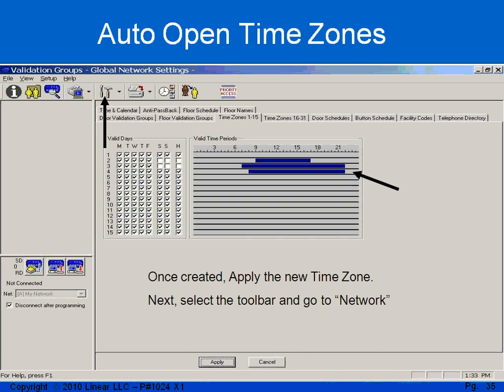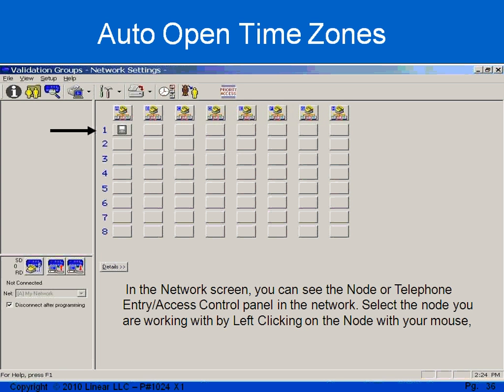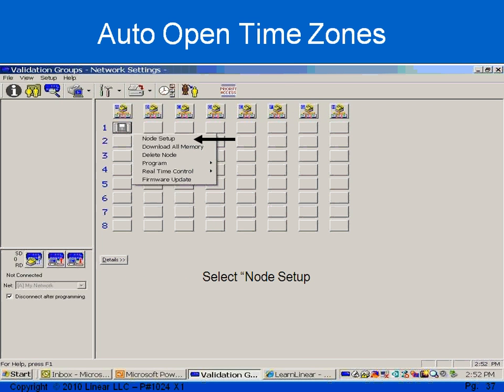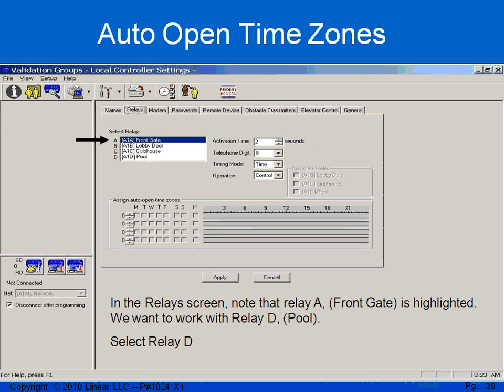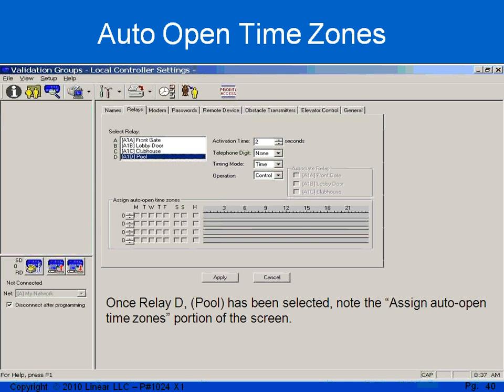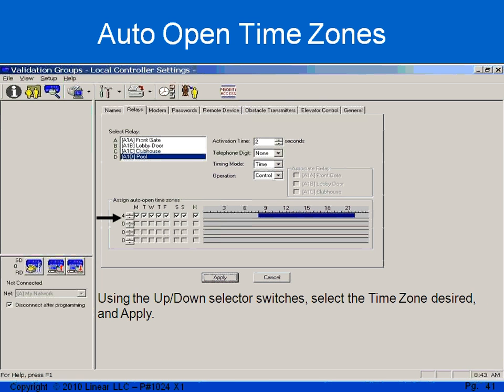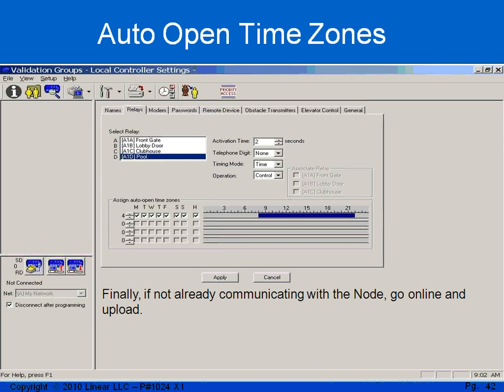Now that I've created my time zone, I need to apply this to the specific relay. The relay is in the panel itself, or the node. So using the hammer and screwdriver to the network screen, I can see in this installation we have one AE2000 Plus in network A address number 1. I select that node and go to node setup. Within node setup, I will see a relays tab. I'll select the relays tab — it automatically goes to relay A, but we want the pool, which is relay D. So I select relay D, highlight it, and down below I see assign auto open time zones. I can have four different time zones per relay, so I'll use my up and down arrows and select time zone 4. Once I've assigned this time zone to the pool, I apply and upload the changes to the node.